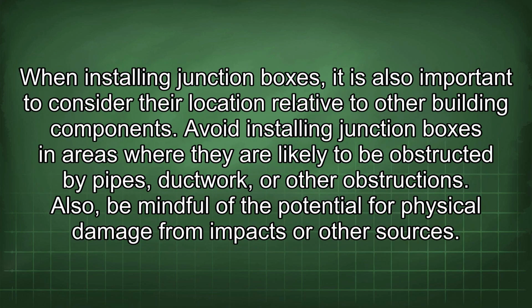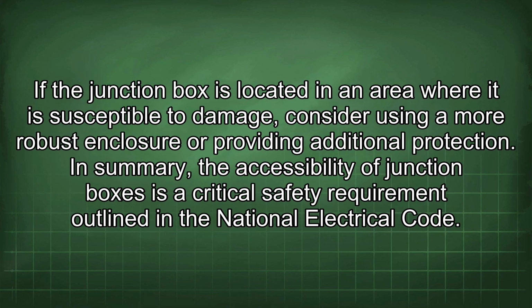When installing junction boxes, it is also important to consider their location relative to other building components. Avoid installing junction boxes in areas where they are likely to be obstructed by pipes, ductwork, or other obstructions. Also, be mindful of the potential for physical damage from impacts or other sources. If the junction box is located in an area where it is susceptible to damage, consider using a more robust enclosure or providing additional protection.